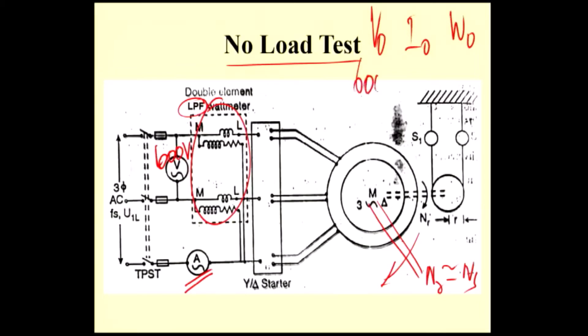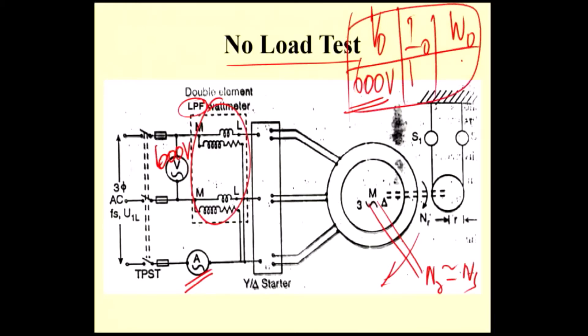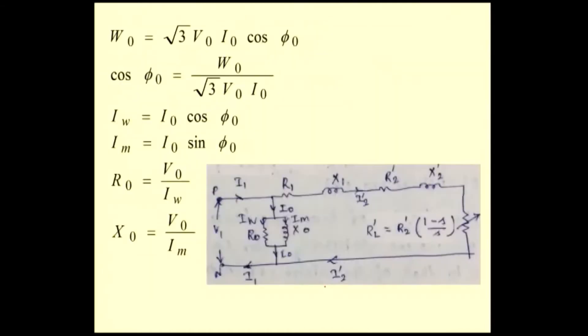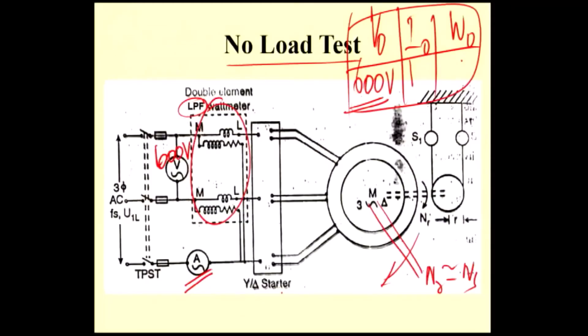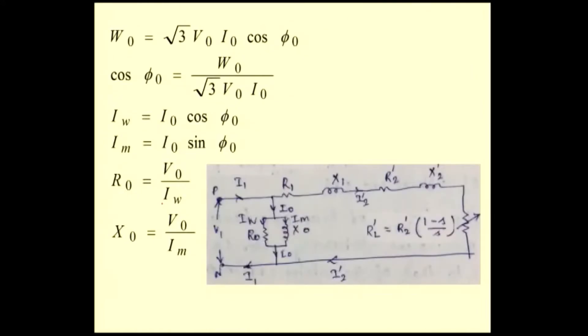V0 is the rated voltage. The condition is: you have to give the rated voltage. At 600V, you record what the current is and what the power is — this is the tabulation. W0 is read from the wattmeter. Using two wattmeters, you add the two wattmeter values and multiply with the multiplication factor. I0 is measured from the ammeter and V0 from the voltmeter. From that, W0 equals root 3 times V0, I0, cos φ0.